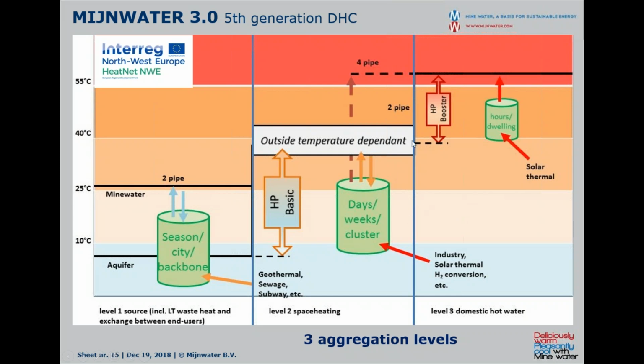From this level of probably 45 degrees in the building itself, and that's mostly like a dwelling, we have a very small booster heat pump. It's about 500 watt electrical, which will raise the temperature of the water which we need for domestic hot water. And also in those dwellings we have a small buffer vessel of 150 to 200 liters, which might also be fed by solar energy.